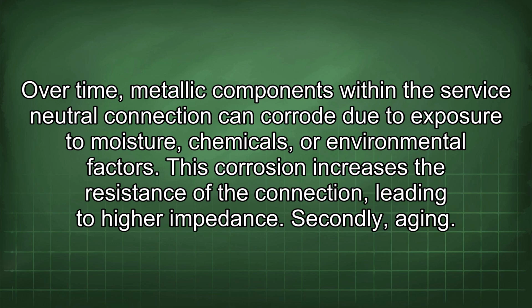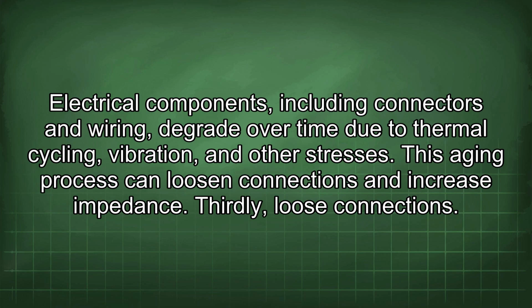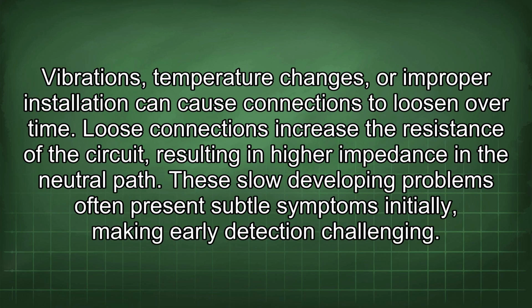Secondly, aging. Electrical components, including connectors and wiring, degrade over time due to thermal cycling, vibration, and other stresses. This aging process can loosen connections and increase impedance. Thirdly, loose connections. Vibrations, temperature changes, or improper installation can cause connections to loosen over time. Loose connections increase the resistance of the circuit, resulting in higher impedance in the neutral path.